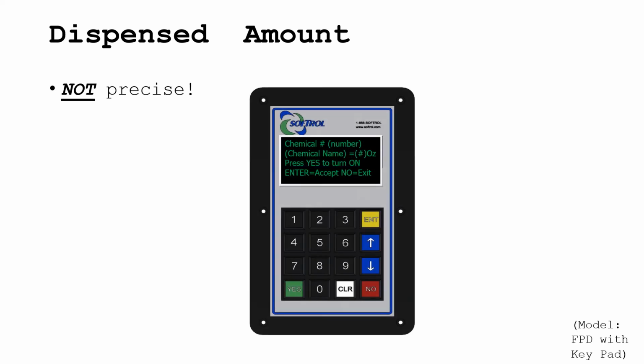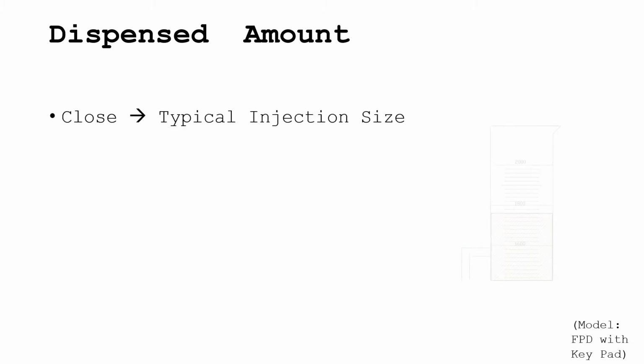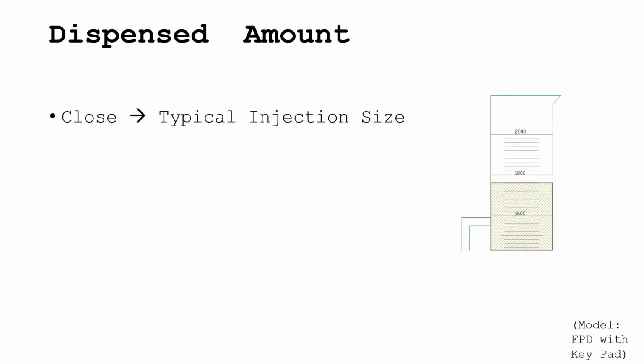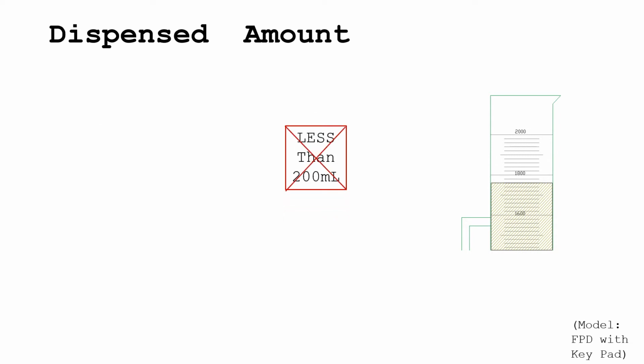When doing a calibration, the dispensed amount does not have to be precisely what you were aiming for. That said, for accurate calibration it is important that you do not stop and restart the pump. You should aim for roughly the typical injection size, but once again, it does not have to be perfect, though the dispensed amount should never be less than 200 ml or more than 1800 ml.